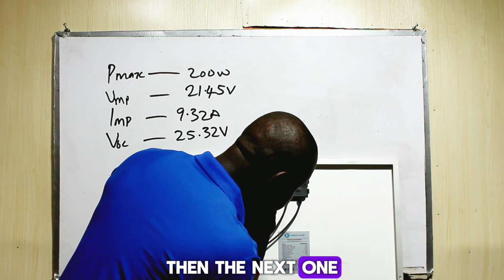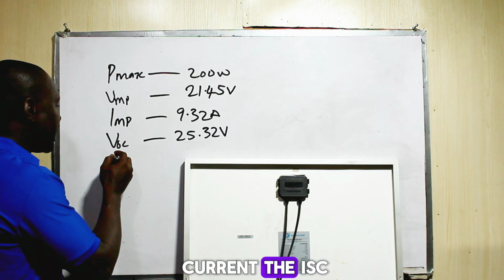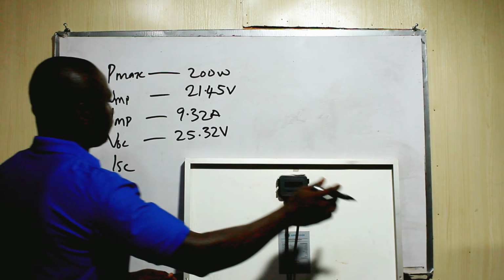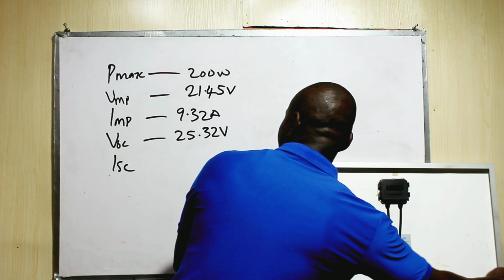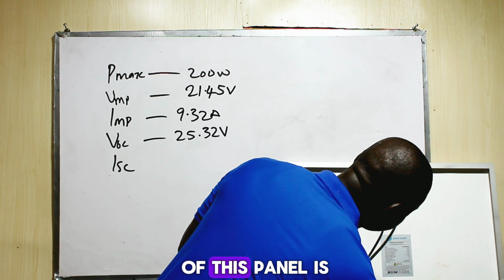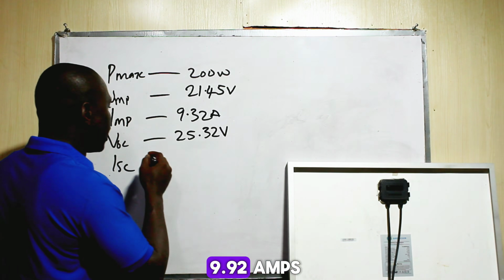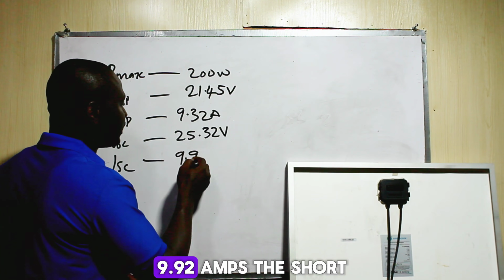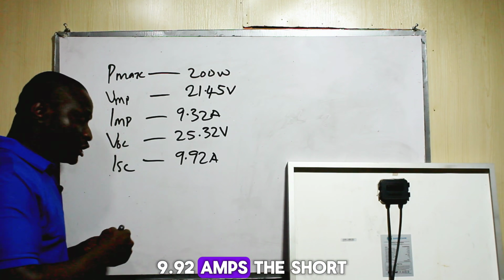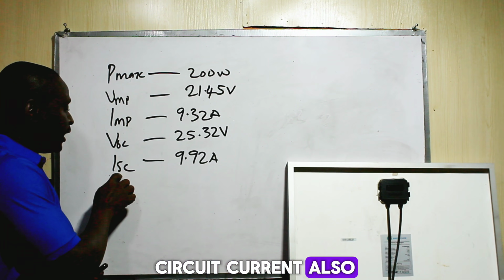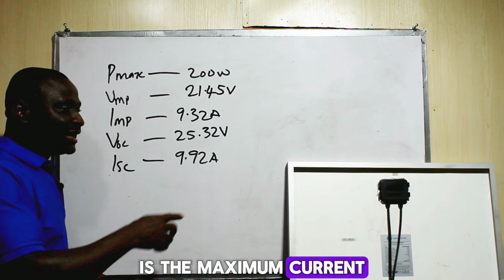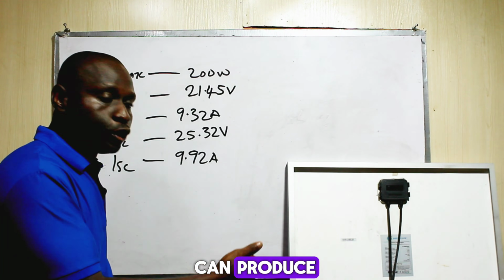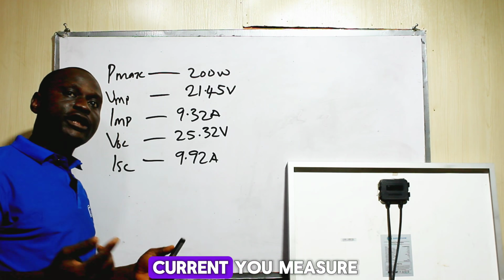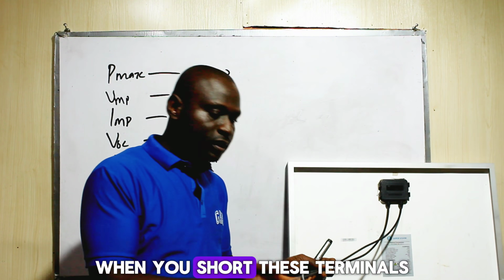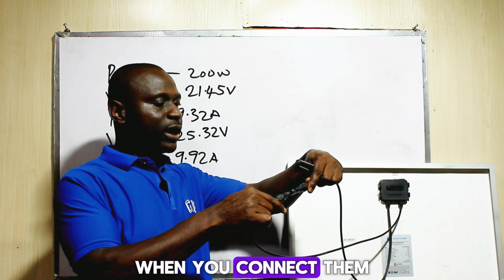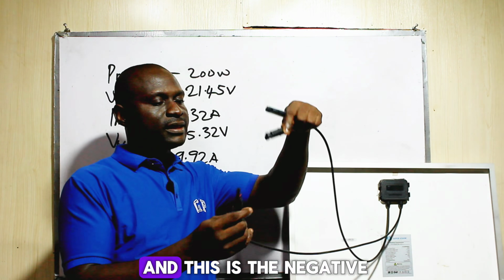Then the next one is the short circuit current, the ISC. The short circuit current of this panel is 9.92 amps. This is the maximum current that this solar panel can produce, and it is the current you measure when you short the terminals, connecting positive to negative.